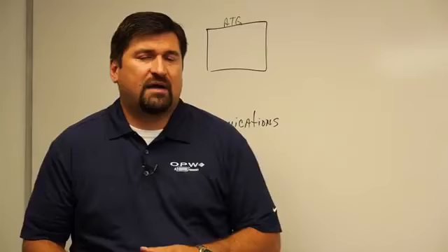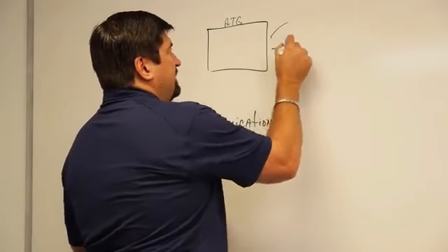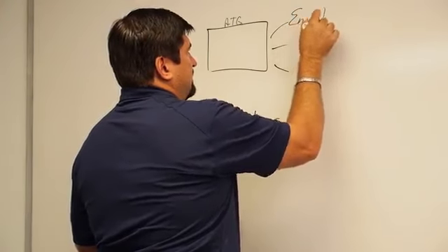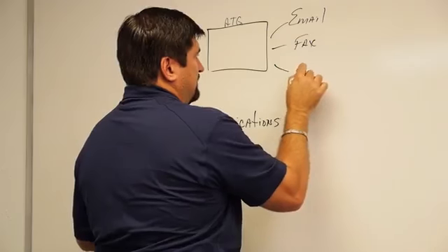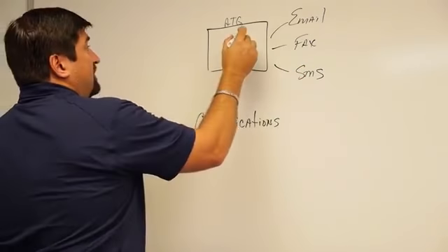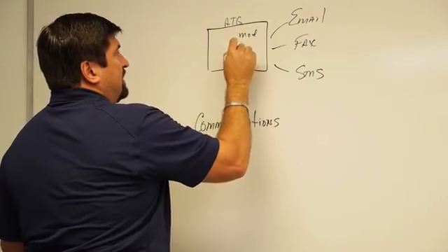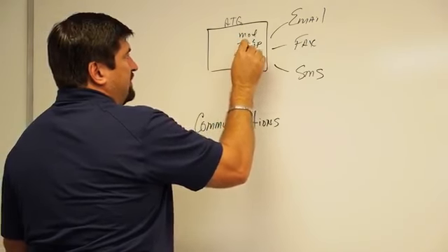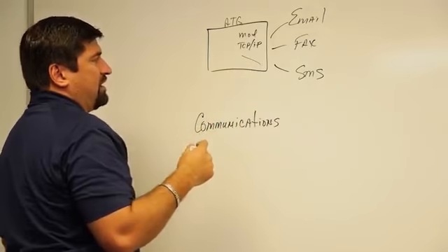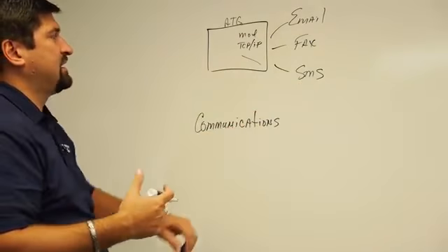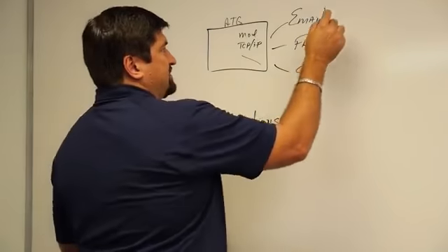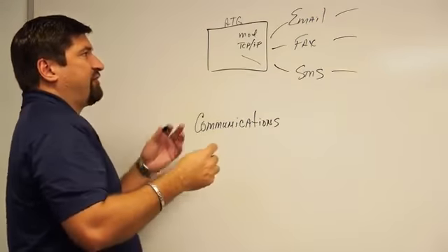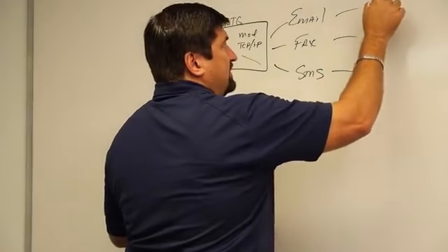And a final note, what we talked about before is the notification piece from the gauge. Most consoles have the ability to have an optional email, fax, or text message capability. When I look at email, fax, and text message, basically what I'm looking for is an optional modem, TCP/IP connection, or some type of external GSM modem to get me the SMS. But if I have email, fax, or text message, I have the ability to push data from the console to, let's say, a delivery company.